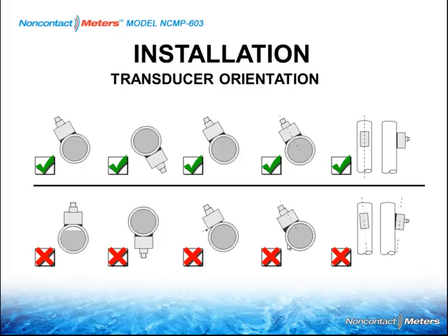People always talk about how much grease do I put on the outside of the pipe. Well, toothpaste on a toothbrush is my answer. The pipe is round, and the transducer is flat. You don't need to take a grinder to the surface of the pipe. We're just trying to remove the loose debris off the top of the pipe. And yes, of course, the insulation must be removed off the top of the pipe.